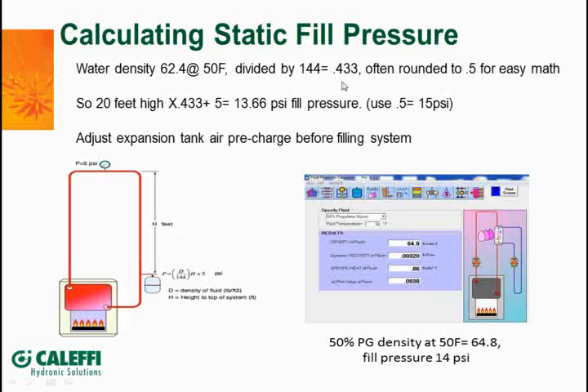Now, what most guys will do with this formula is they'll round that 0.433 off to 0.5 just to make the math easier. It's really easy to do it in your head. If you've got a 20-foot high building times 0.5, you need 10 pounds plus 5 gives you 15. So round that up to 0.5, and that would give you 15 pounds. You can see there's very little difference between the 13.66 and the 15 psi. So that's what your fill pressure needs to be for that job.